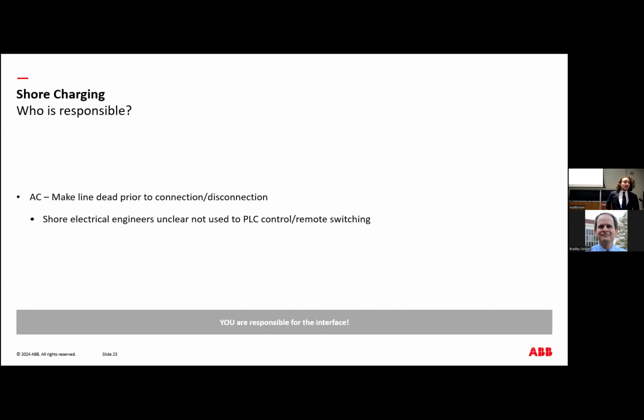The second lesson: anytime you have a shore charging connection, you need to make the line, or the mains, dead before you plug it in. This is like plugging something into an outlet—you don't turn it on before you plug it in, because it will arc. An arc at 480 volts is dangerous. An arc at 12 kV is explosive.